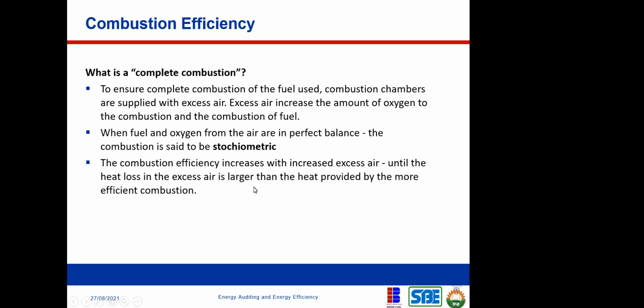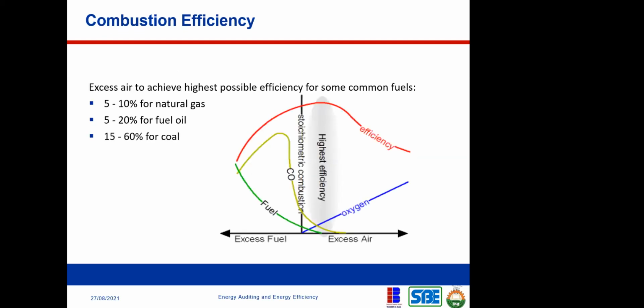So this holds until the heat loss in the excess air is larger than the heat provided by the more efficient combustion. I will explain this. I think I've actually explained it: for the fact that you don't know the amount of oxygen that you need to achieve complete combustion, it necessitates that you include excess air. So excess air is needed to achieve the highest possible efficiency for some common fuels. Let us look at some of them. For natural gas, it is advisable that you add about 5 to 10% excess air to achieve complete combustion. Then for fuel oil, about 5 to 20% excess air. Then for coal, about 15 to 60% excess air to achieve complete combustion, right?